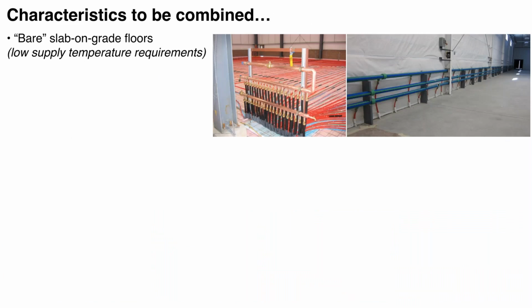And what are these characteristics we want to put together? Well, a bare concrete slab, and any of you that have worked with floor heating know that a bare slab has one of the lowest water temperature requirements of any radiant floor heating system compared to, for example, a plate system where the plates are installed above the floor or below the floor, or a thin slab system on a wooden floor. So as building envelopes get tighter, the water temperature requirements go down. So we're looking for these bare slab types of buildings.